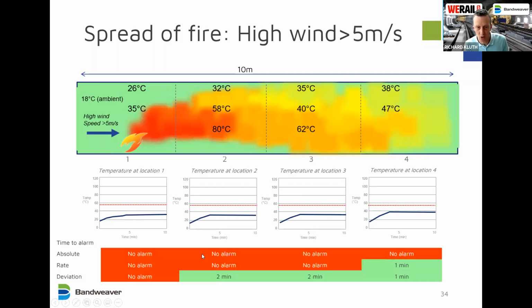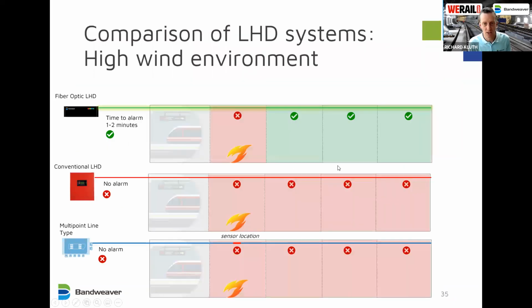And which alarms do trigger? It's a mixed picture. Deviation in some zones, rate of rise in some zones, but not in others. So which systems would trigger? So the fiber optic triggers in 3 out of the 4 zones. The other systems would not trigger within that time frame. So again, it triggers within 1 to 2 minutes.